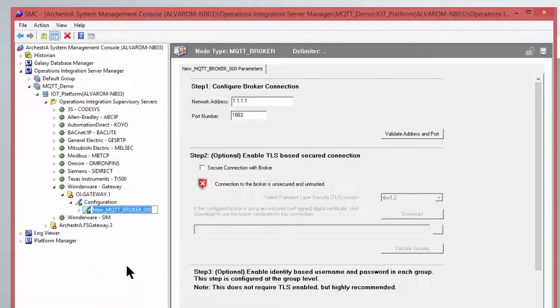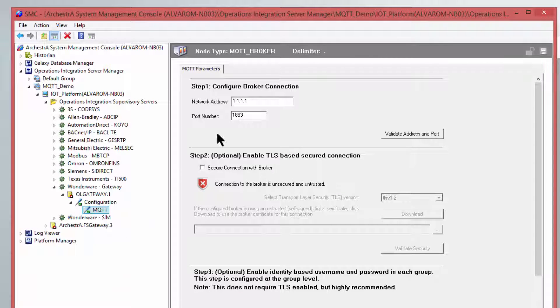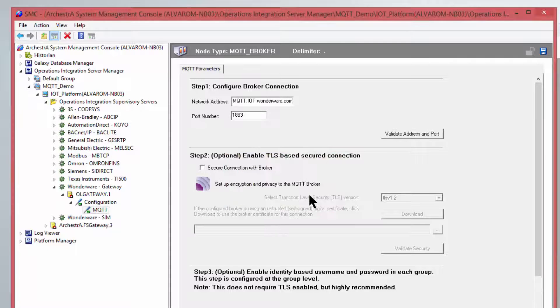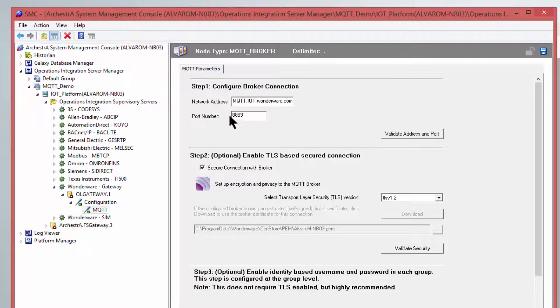In our new configuration, we have a way to create an MQTT connection to a broker. We actually also have a test broker at MQTT.IoT.Wonderware.com, and as soon as you create it, you can actually validate the connectivity there. We also give you a secure connection. By default, the unsecured port is 1883, but if you want to try it with a secure connection, you can do so.